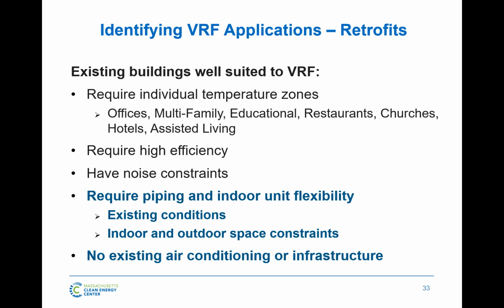heating and cooling. You're typically going into a building, usually with some architectural sensitivity, that needs to be, or it's much easier to run this flexible refrigerant piping that's very small rather than to start running ductwork where you may not have the room for it, whether it's low ceilings or not having chases in the building. That's the type of thing where VRF can really help out, is just getting into those tight spaces that require a little bit more flexibility.